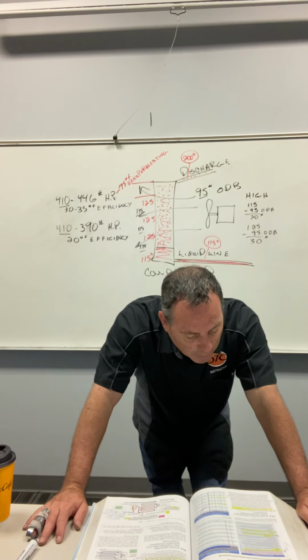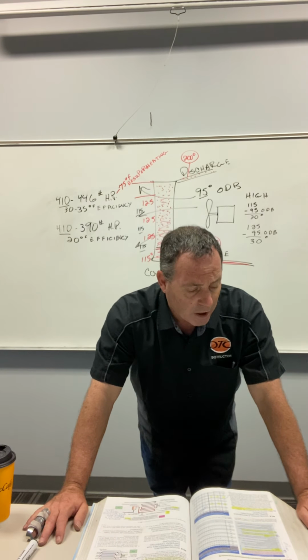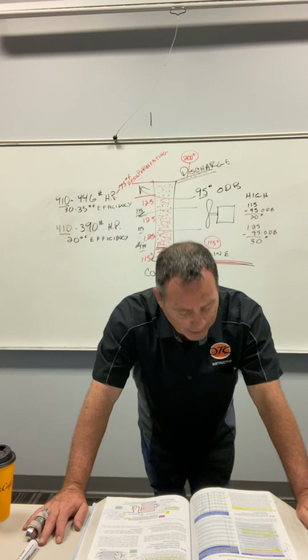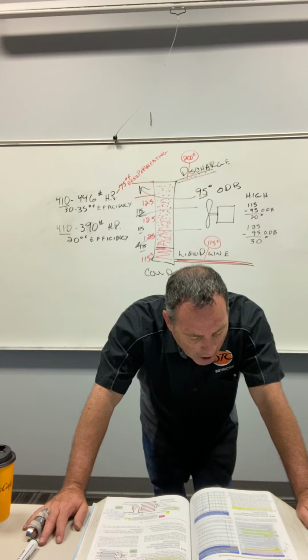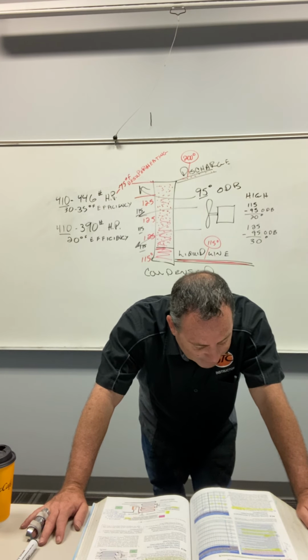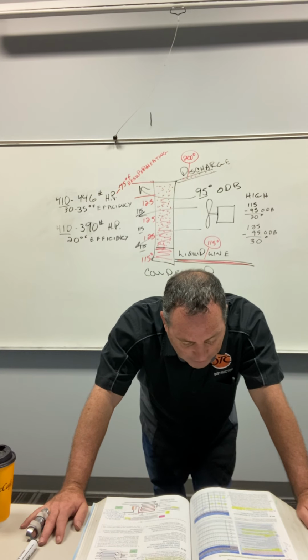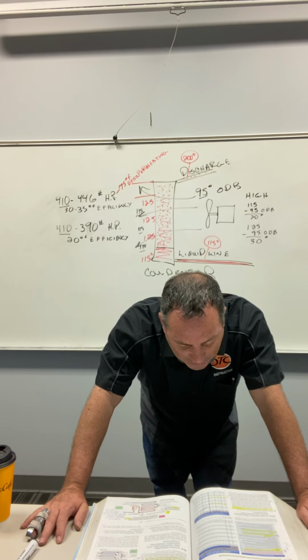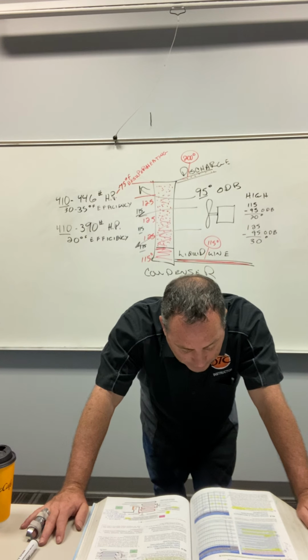Now in 1224 it says, when you have no literature or nothing to help you, what do you do? The first thing is to establish some known condition. Try to see if it's high efficiency, low efficiency. See what the compressor is. Look at figure 4012 right there, 1224. It says approximate full load amps for these alternating current motors.